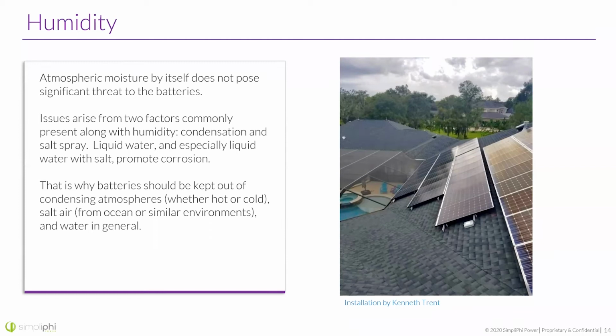Looking at stuff like our NEMA 3R enclosures, that's if you're going to install outside. So actually this one right here, installation by Kenneth Trent, he has done a lot of access units I know of. So those are all-in-one ESS solutions in Florida and other areas that do see high humidity. So I know for a fact these have sat in that NEMA 3R enclosure and been okay in these high humidity areas, not seeing salt spray, not seeing that actual liquid water form.